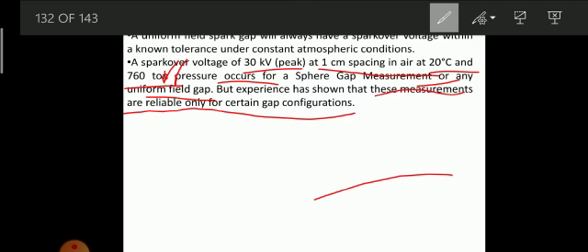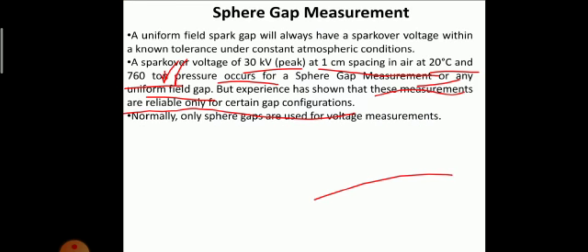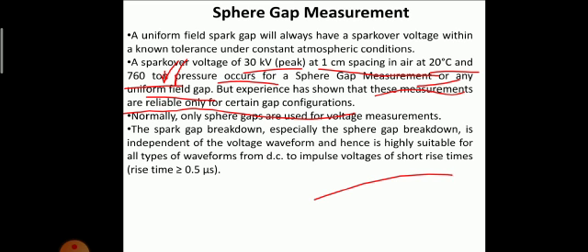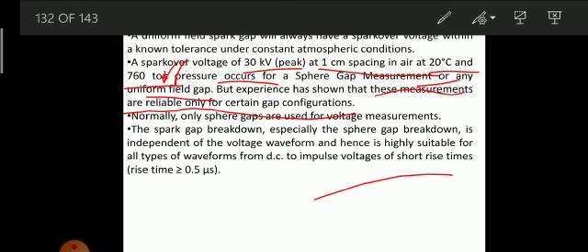Normally only sphere gaps are used for voltage measurements. In certain cases, uniform field gaps and rod gaps are also used, but the accuracy of rod gaps is less as compared to sphere gaps. Next, the spark gap breakdown, especially the sphere gap. A spark gap can be a sphere gap, a rod gap, or a uniform or non-uniform gap, but here we are talking about the sphere gap.